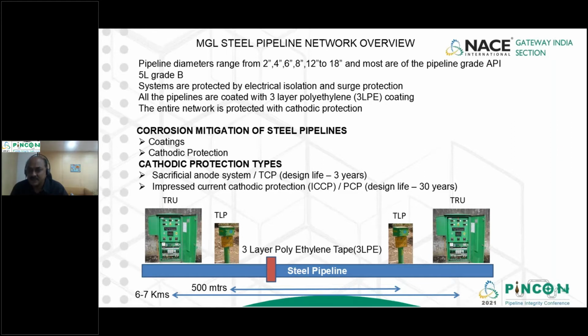Our systems are protected by electrical isolation and cathodic protection. All pipelines are coated with 3-layer polyethylene coating, and we do have some sections of pipeline with fusion bonded epoxy, but most of them are 3-layer PE. The entire network is protected with cathodic protection. So corrosion mitigation in steel pipelines is by coating and cathodic protection. The cathodic protection types are a sacrificial anode, which is known as temporary cathodic protection with a design life of 3 years. And we have an impressed current cathodic protection system, which is a permanent cathodic protection, which has a design life of 30 years. We have TLPs, test lead points, every 500 meters, and every 6 to 7 kilometers we have a TRU.